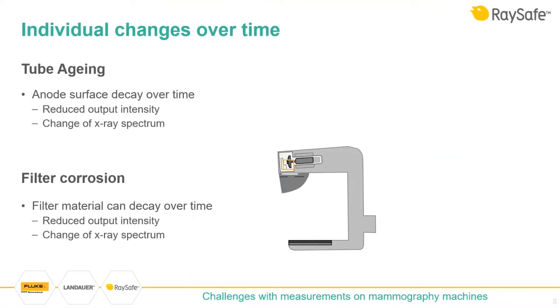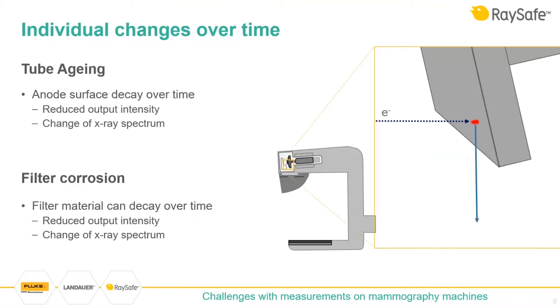On top of model-specific differences, you have individual changes on the machine that happen over time. For example, tube aging results in reduced output intensity and changes the X-ray spectrum. When the anode surface becomes rough, you get increased HVL and reduced dose output. You have the same effect with filter corrosion — not all materials corrode, but some do, resulting in reduced intensity and a changed X-ray spectrum.